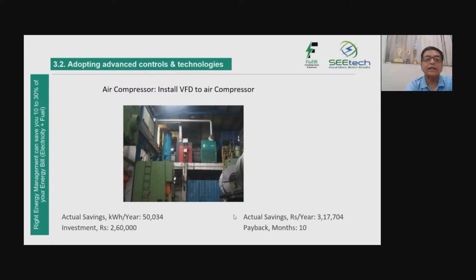Your compressor requirement is not continuous, it is there in batches. And when it is in batches, your compressor will go on no load, right? Even in that condition it is consuming 30 to 35%. So you need to install a variable frequency drive on it. As your pressure reaches towards the no load or high load pressure, the compressor will get on load or off load based on pressure, and accordingly the VFD changes the RPM of the motor. So this gives significant savings.